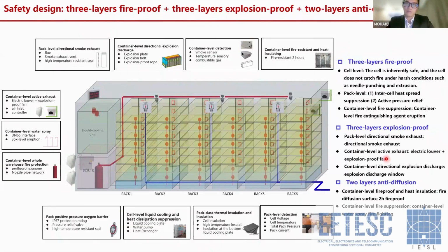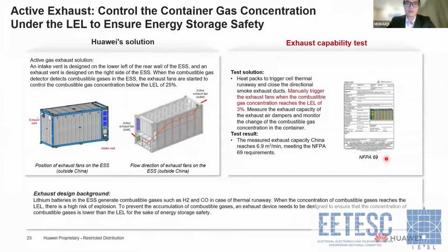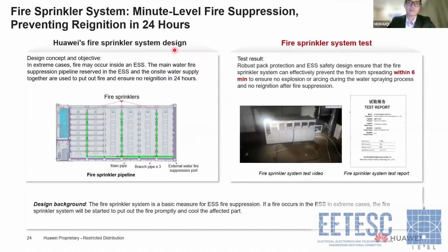So this is our fire extinguisher system, what we design and what we consider. I think for Sri Lanka, today all the guys who come here should be engineers. So when we check the system and do the design of the system, maybe we can consider this more. These are some principles to introduce how we do the active exhaust. We can see there are active exhaust fans. If something is released, we can use these fans to get everything out. Another one is the fire sprinkler system. In some regions, if you want the fire to be eliminated as soon as possible, you can also connect water to do water sprinkling to make the whole system cool down as soon as possible.